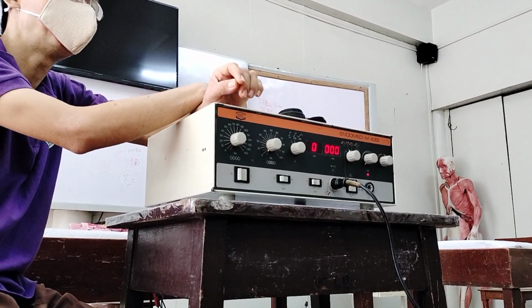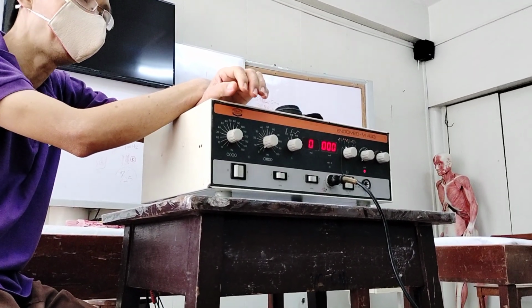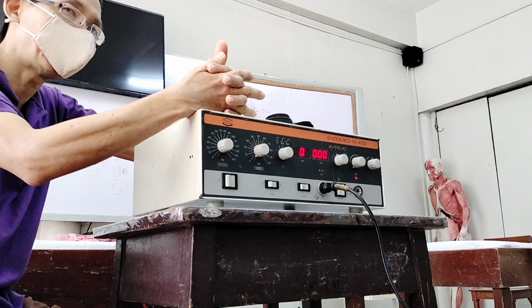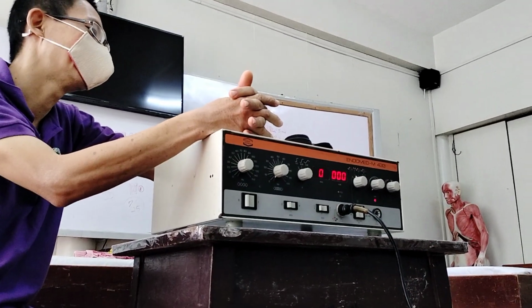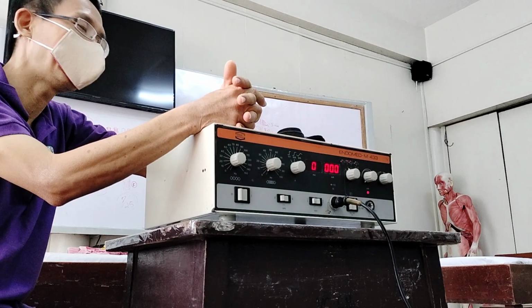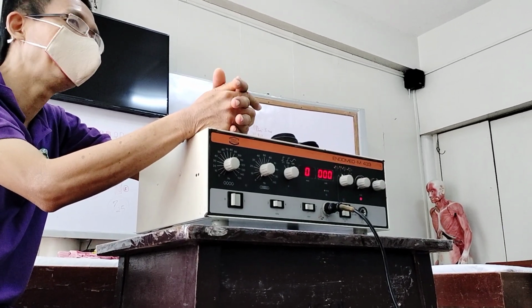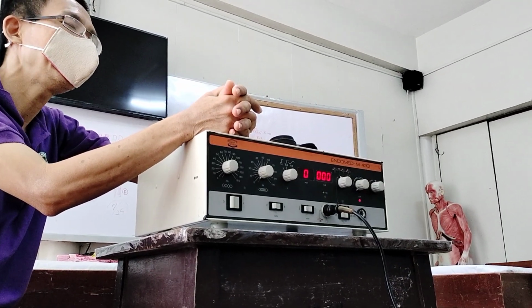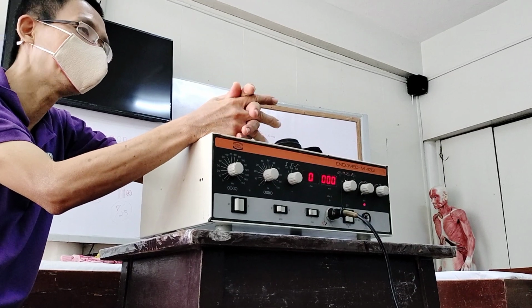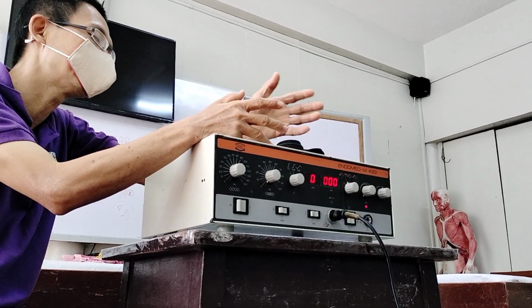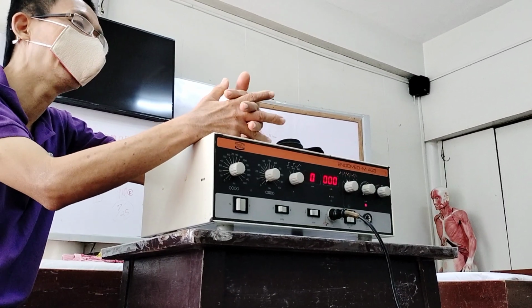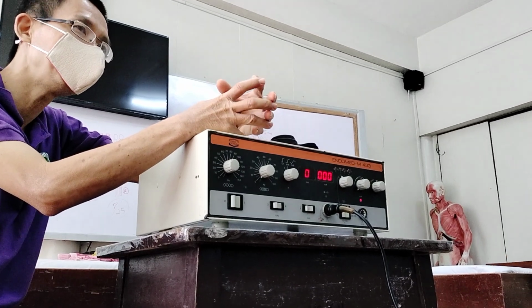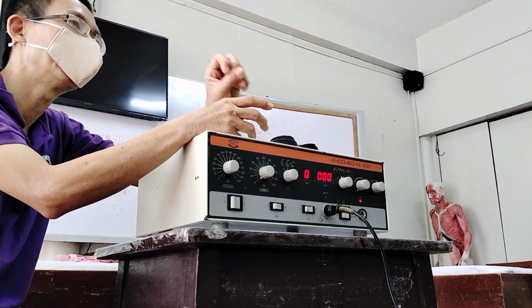Another advantage of two-pole or bipolar is that the interference effect is always 100%. The interference of the medium frequency current is always 100%. One of the problems or concerns with two-pole or bipolar is that the intensity it produces is greater as compared to quadripolar, and we're going to discuss that later. The current produced in bipolar is already the combination of the two medium frequency currents, so it is stronger and more intense.